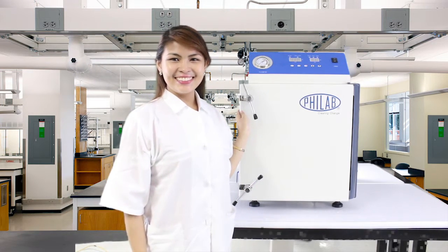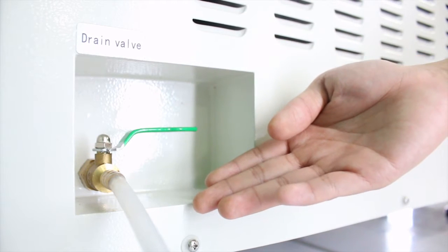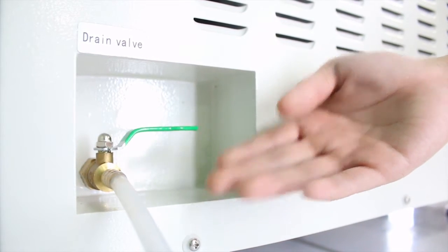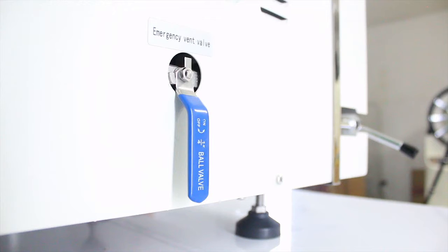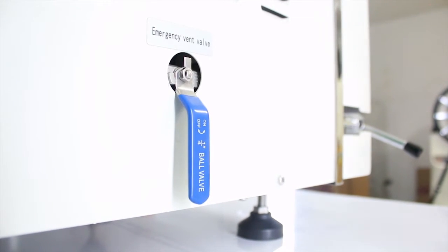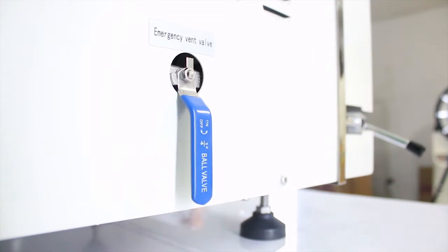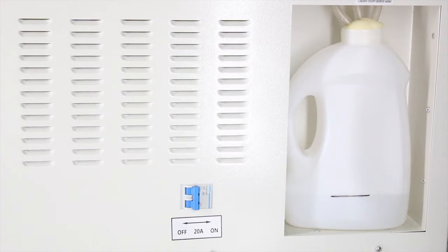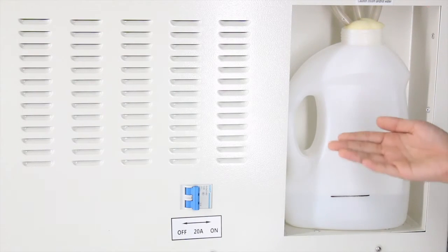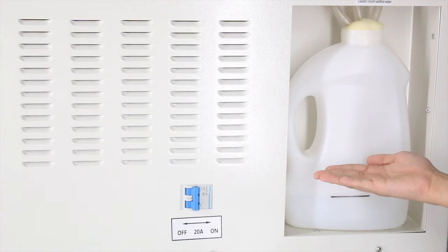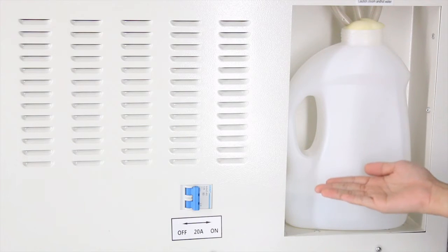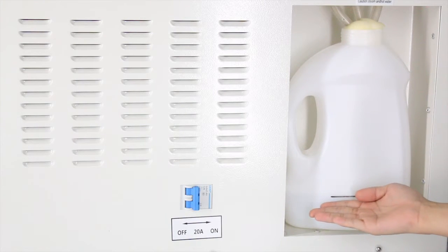On the left side of the autoclave, you will find a drain valve which drains the water from the chamber. There is also an emergency vent valve which releases pressure from the chamber. On the right side, you will find a white plastic bottle. This is the steam release bottle. It should always contain some 3 inches of distilled water from the bottom of the bottle.